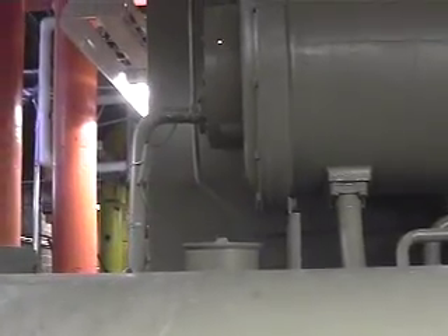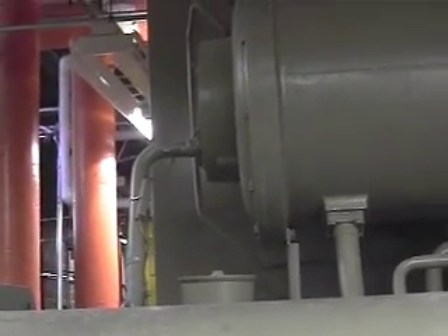Sends it out to there with your roller ball bearings. It also goes into the front of the compressor, which I'll show you on the other side, which also feeds and lubricates your bearings there. When I was talking about your refrigerant cooling on your chiller, there's your line right there. See that little flat piece of metal in between the flange and the compressor? That's the orifice plate that I was talking about that creates a flashing effect. It cools your compressor.